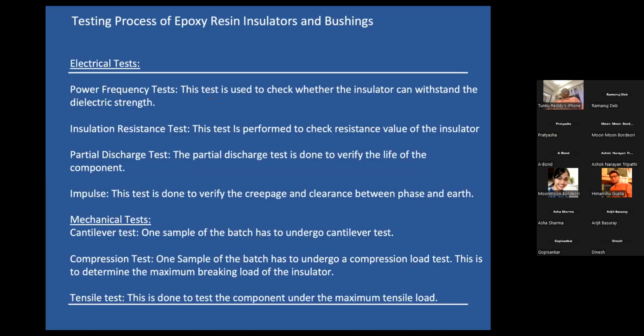Now, what are the tests required for insulators and bushings? The power frequency test is a very important test. It is used to check whether the insulator can withstand the dielectric test strength. The insulation resistance test is also used to check the resistance value. Partial discharge is done to verify the life of the component. Impulse is done to verify creepage and clearance between phase and earth.